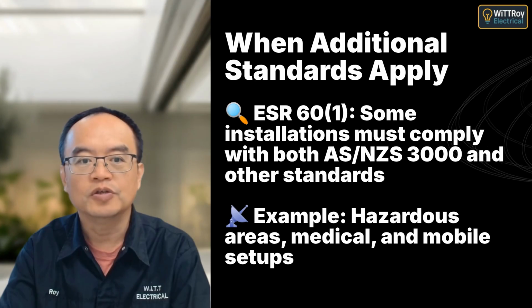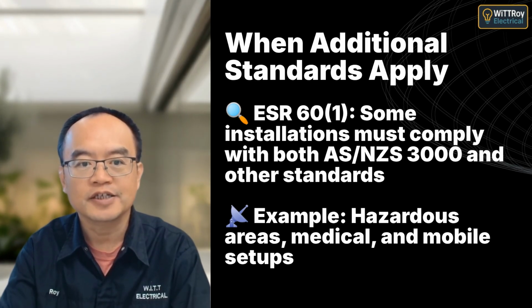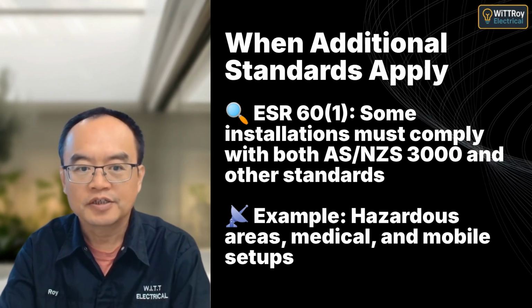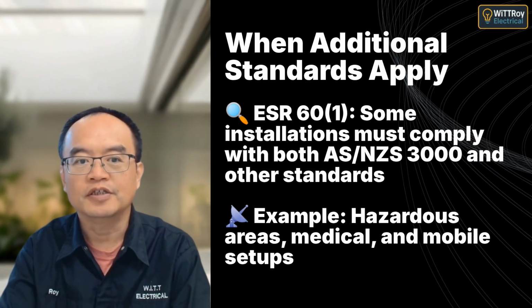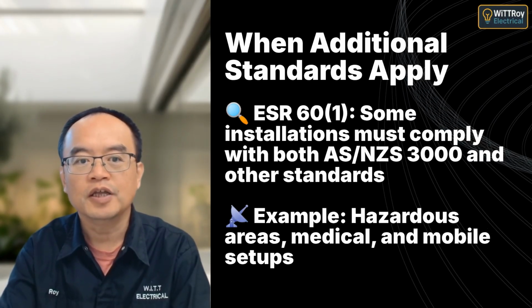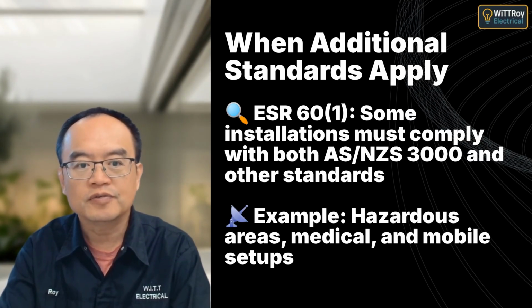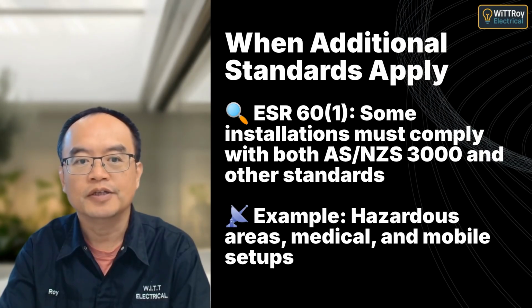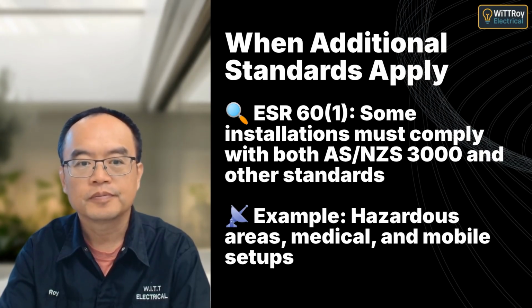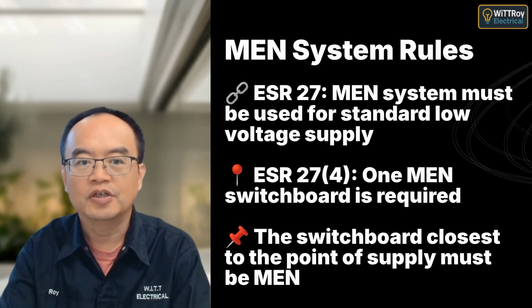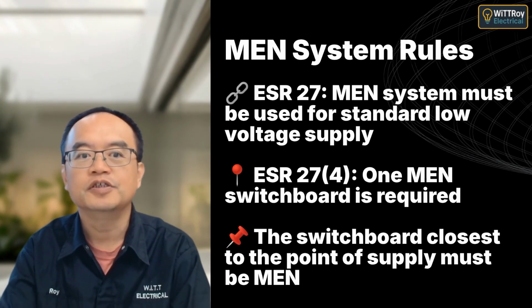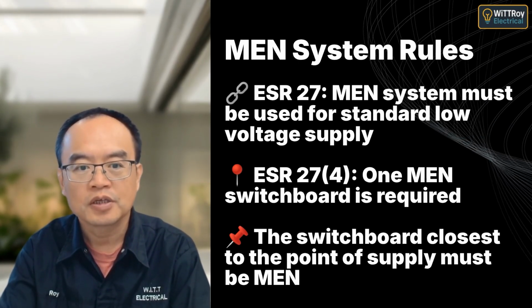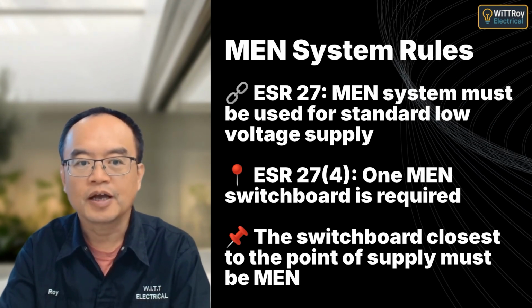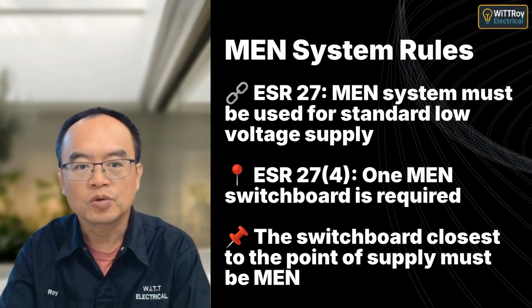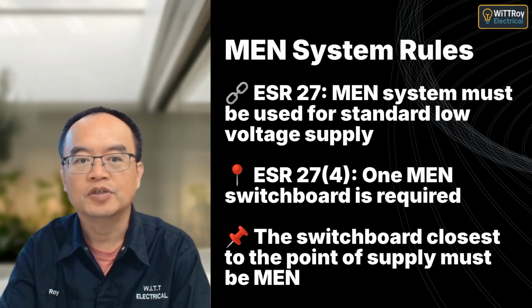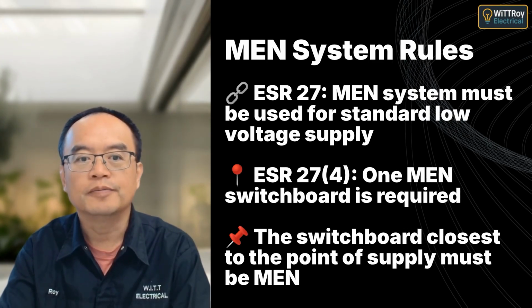Some electrical work falls under other standards in addition to AS/NZS 3000. ESR 60.1 ensures that if another cited standard applies, it must also be followed, like AS/NZS 60079.17 for hazardous areas. According to ESR 27, every standard low voltage installation must use a multiple earth neutral MEN system. At least one MEN switchboard is required, and it must be the one electrically closest to the point of supply.